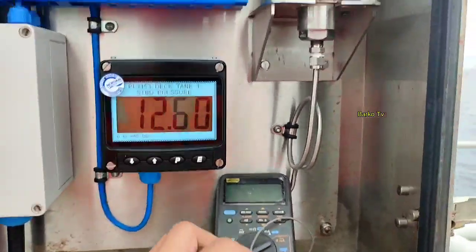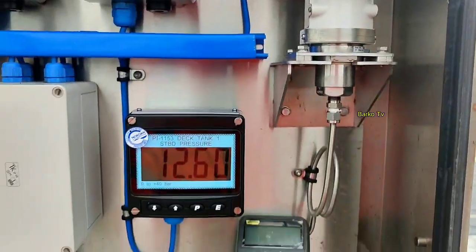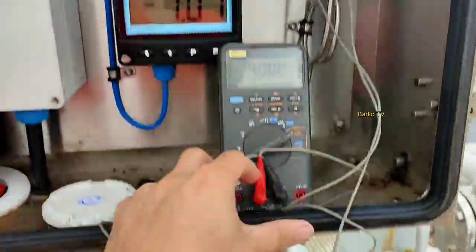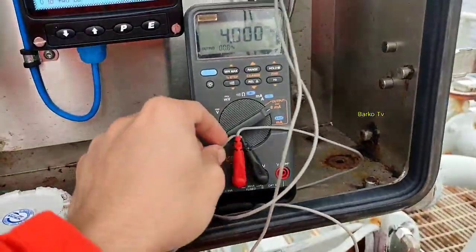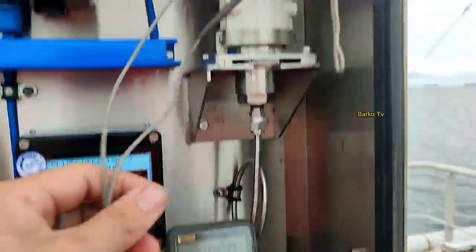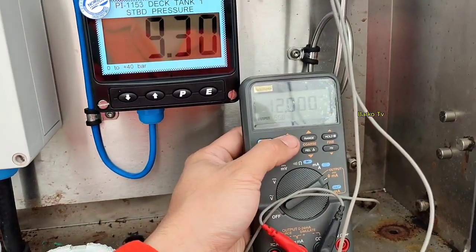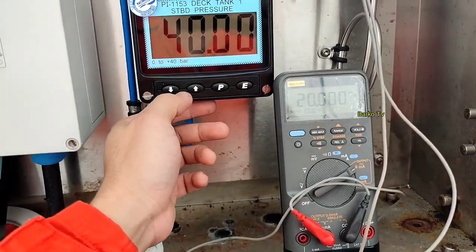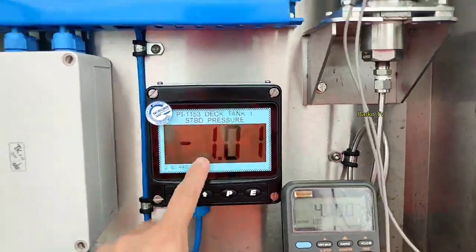This confirms the correct set point: minus 1 to 40. The other option is to do a loop calibration. We check simulation — at 4 milliamps we verify the reading, and as you can see it shows minus 1.01, which is good. Then go to 20 milliamps — the range shows 40, confirming our range setting is now correct.